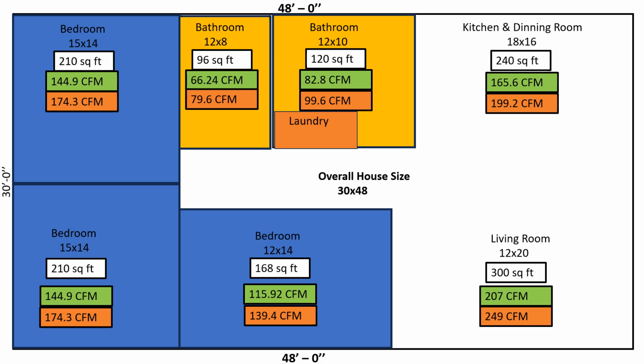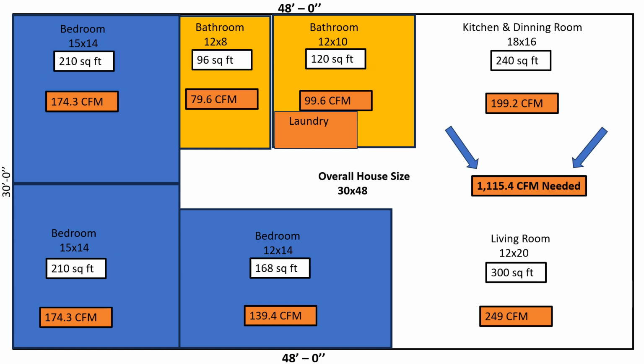But let's say, for the sake of this podcast, we went strictly with a 3 ton unit. So let's get rid of the 2 ton and 2.5 ton numbers and stick with our 3 ton numbers. Now I'm looking at that bedroom needs 174. Well, we just said 8 inch carries 160. So now my 8 inch is going to be too small because I need 174. So here's where your options come in. I can take two 7 inches and put them here and turn one down, or I can put a 7 and a 6 inch. Same way here, a 7 and a 6. That would give me quite a bit more airflow, and then I would size it down and damper down whichever one I needed.